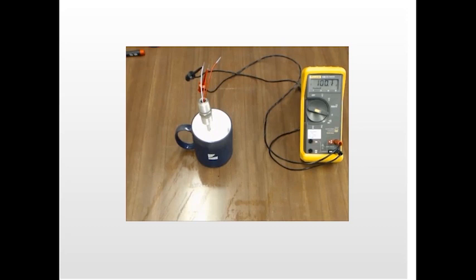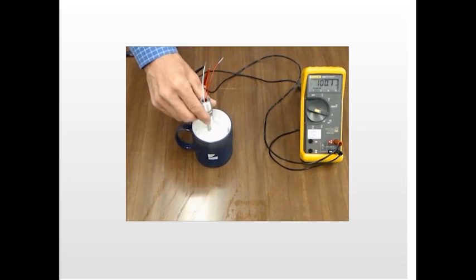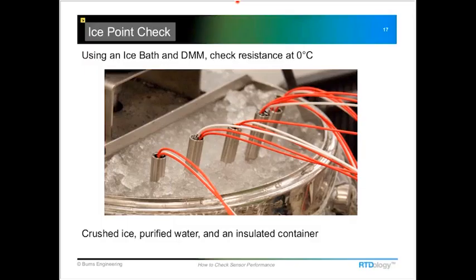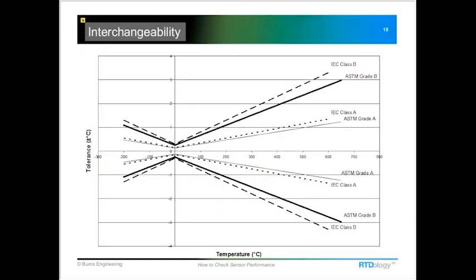And this number is going to jump around a little bit, and it's just kind of a bad way to do it. So again, it's got to be an insulated container, with enough ice to fill it up completely. Pour in enough water to come up to within about an inch or a half inch of the top of the ice. And then when you place the probe in there, you need sufficient immersion length to overcome any kind of stem conduction, which for 1/4 inch diameter probes is usually about 4 inches. And you want to make sure that the probe does not touch the bottom of the ice bath. You need to leave a little bit of space at the bottom. So, real simple check to do, and it gives you a good, accurate number of how it compares to the original manufacturer's specifications for it.